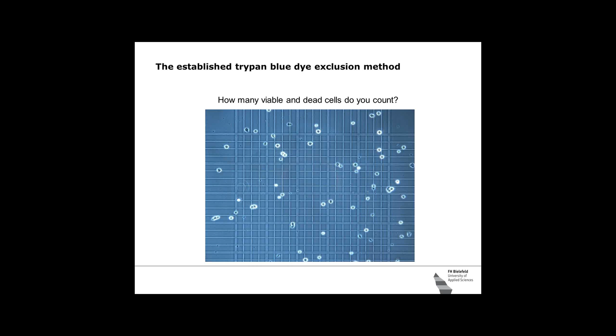And this is what we see here. We have 4 different operators, and we gave them a set of samples, and they didn't know that 4 samples were the same, and asked them to count the cells and to write down and document the cell concentrations. And this is only cell concentration. It's not viability. And you see that the deviations are sometimes, here operator 2, from an average of 800,000 cells per milliliter to over 1 million, more than 20% by the operator.